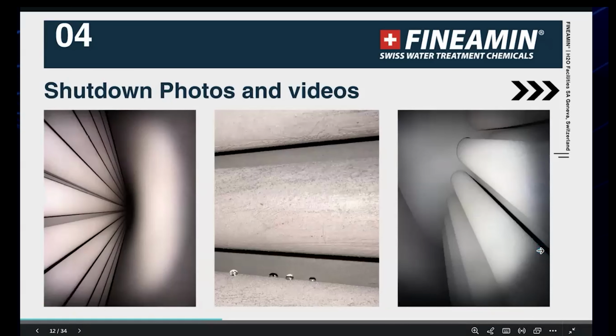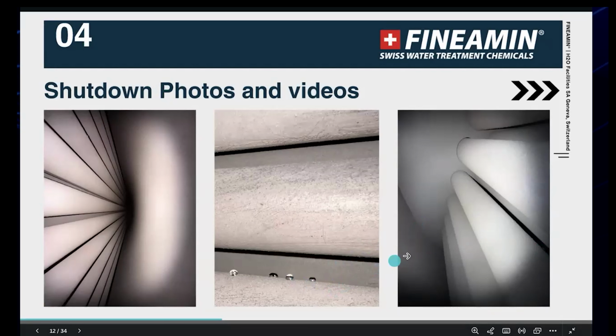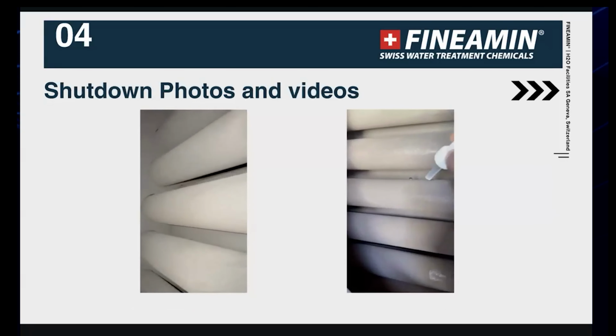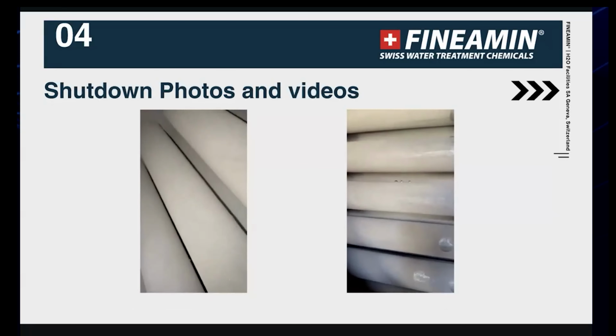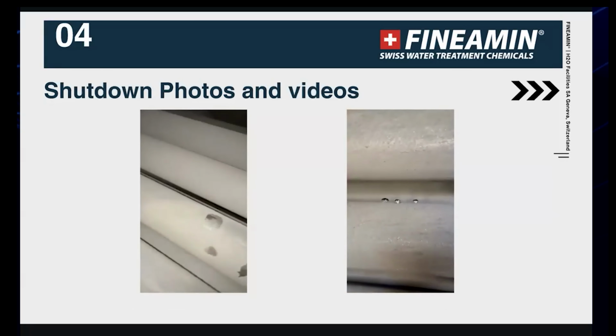We can see some photos from the shutdown. This can give you a close look at the filming amine and the hydrophobicity of this layer, and how the drops of water are not wetting the surface of the pipes. And these are also videos. You can see how the drops slide directly. In fact, this helps much for not accumulating more scales.